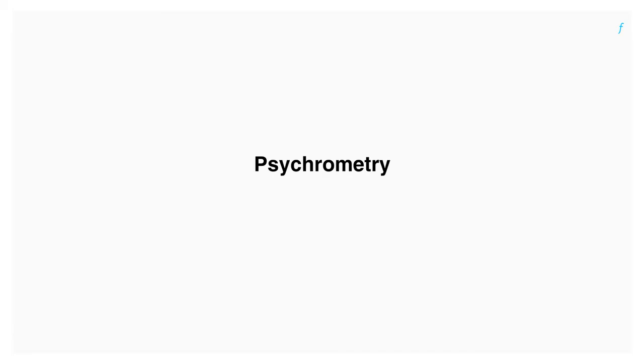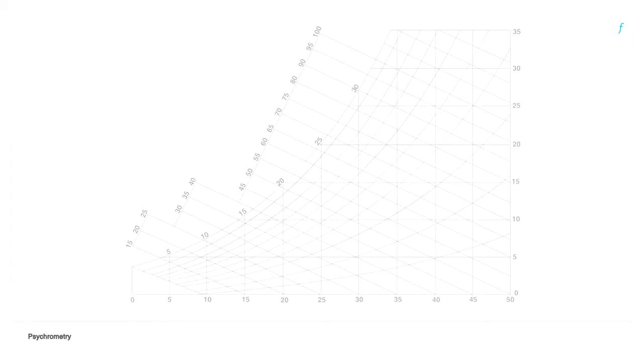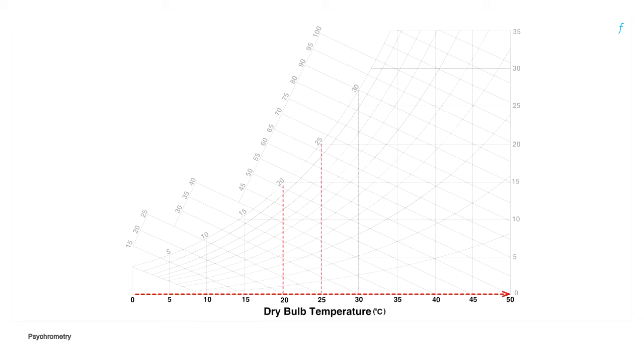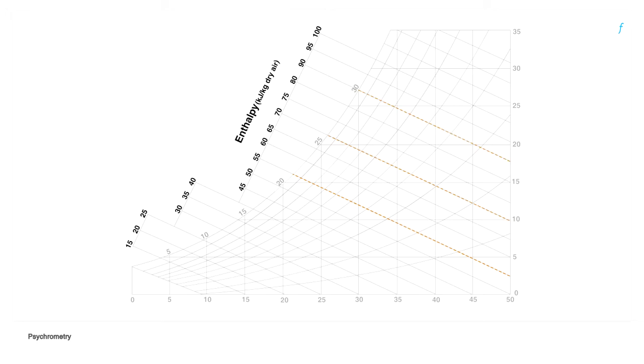Psychrometry is the study of moist air and psychrometric charts are the tools used to study them. Let's have a look at the elements of this chart and use them as a reference to understand evaporative cooling. Dry bulb temperature is represented on the x-axis and increases as we move from left to right. Wet bulb temperature lines are inclined and straight, increasing from left to right along the highlighted curve. Enthalpy lines are also inclined and straight and increase in the direction of the highlighted curve.